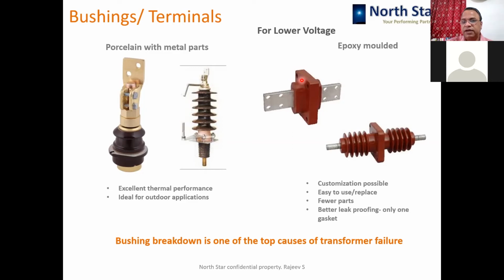they have other defects, like their thermal behavior is not that good. In solar transformers particularly, we see that these kinds of bushings are not able to withstand the thermal dynamic stresses, and they give way and leak. So our service team spends a lot of time attending to these kinds of issues when transformer bushings have failed in solar applications.